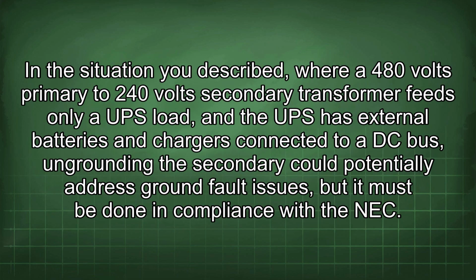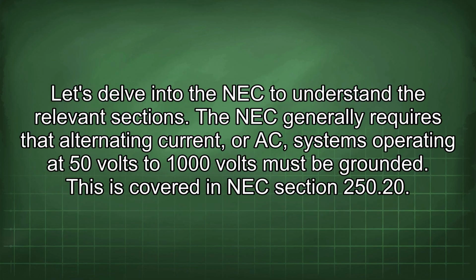In the situation you described, where a 480 volts primary to 240 volts secondary transformer feeds only a UPS load, and the UPS has external batteries and chargers connected to a DC bus, ungrounding the secondary could potentially address ground fault issues, but it must be done in compliance with the NEC. Let's delve into the NEC to understand the relevant sections.